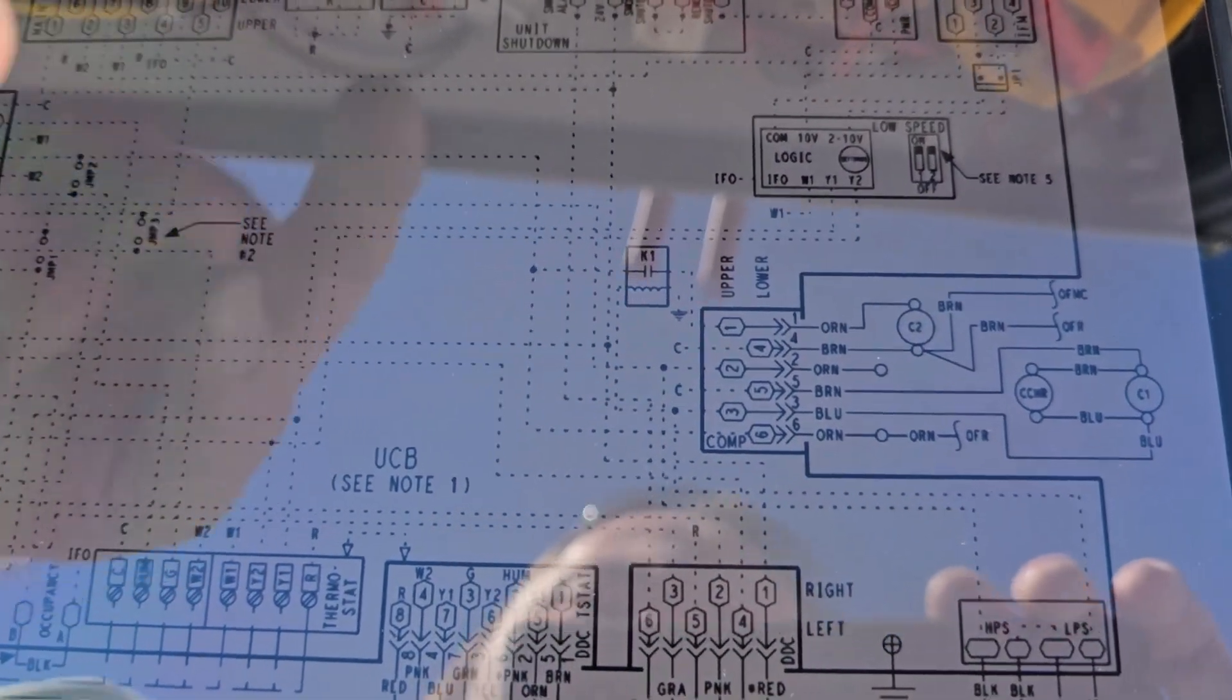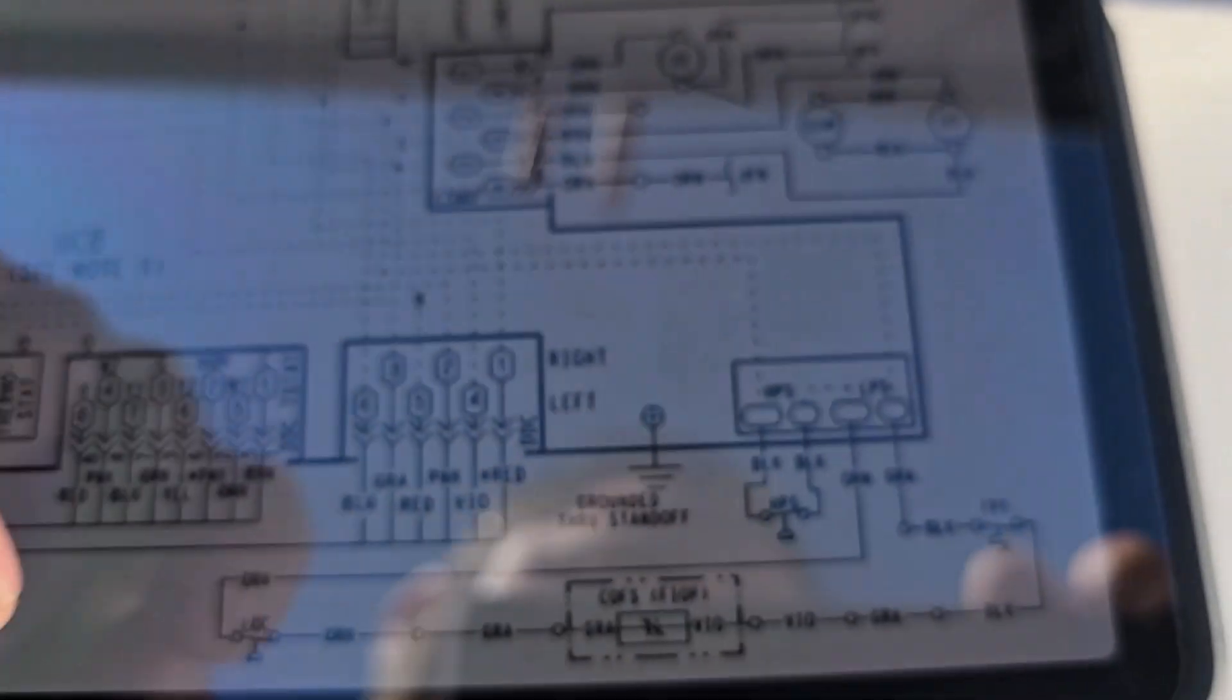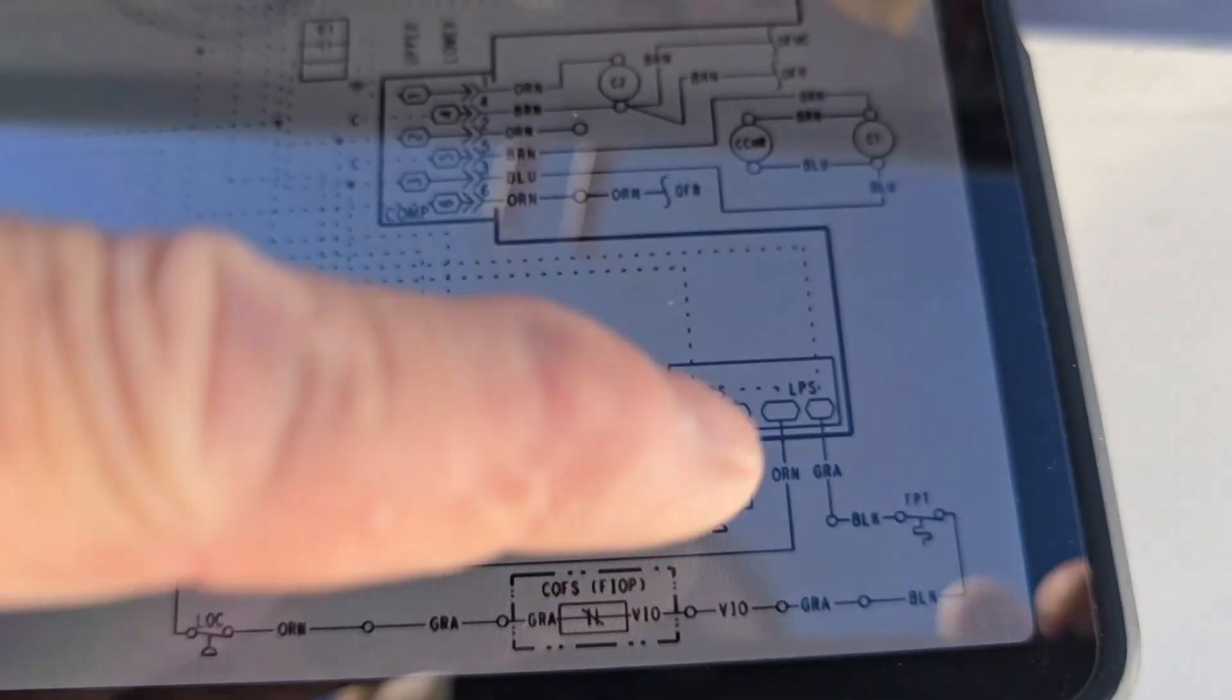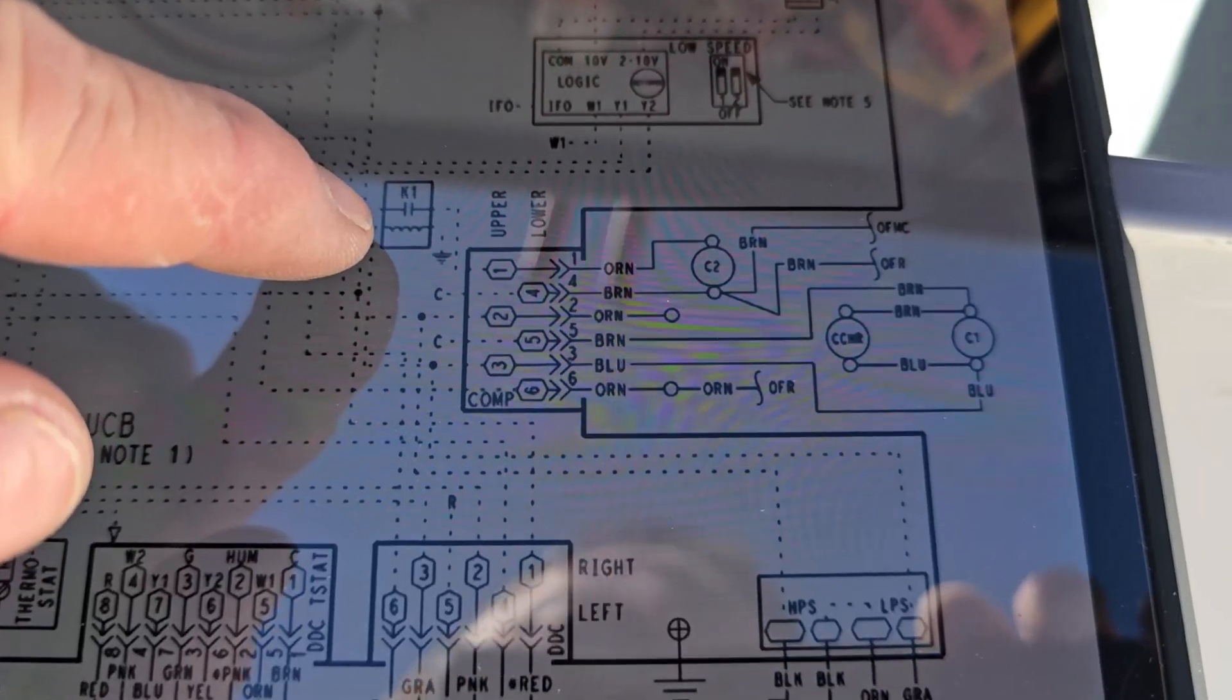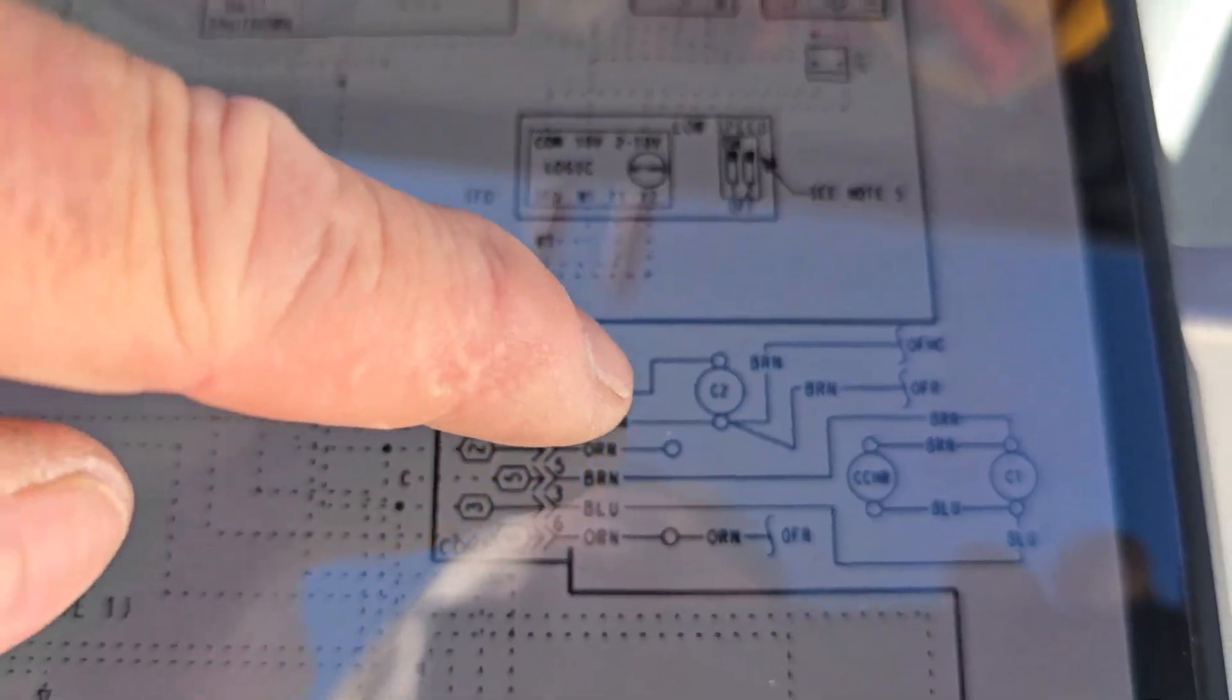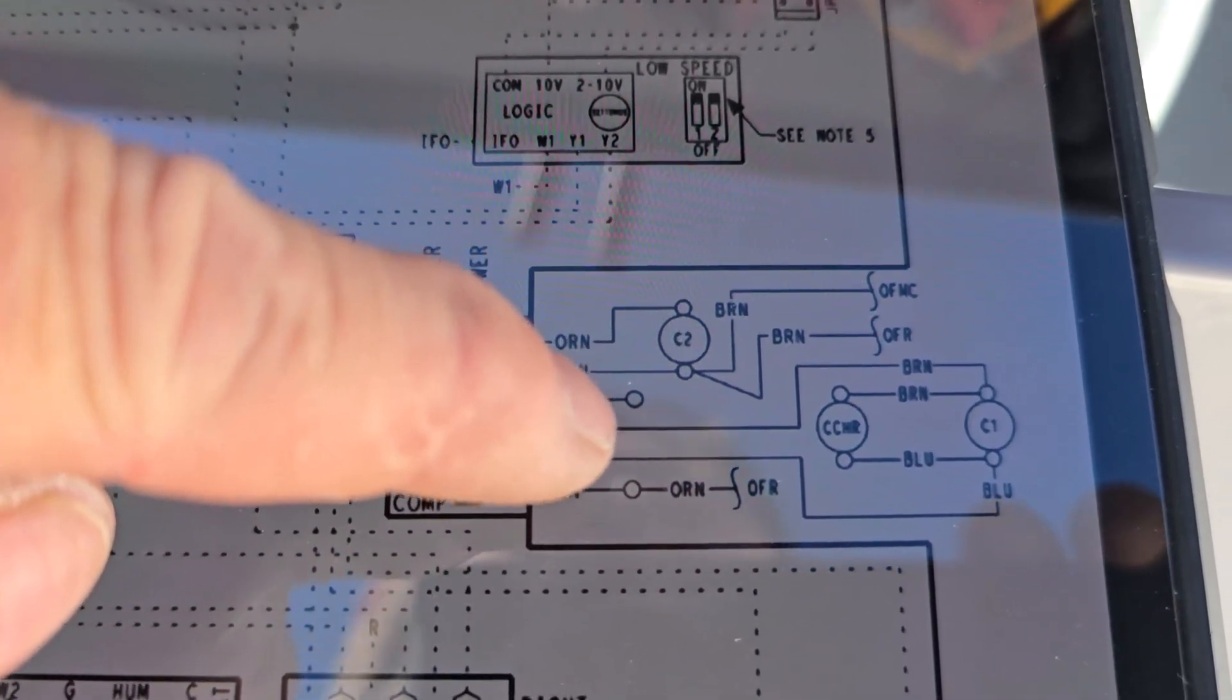So it's bypassing safeties and everything, because Y1 comes down and goes through your safety chain down here, you know, low pressure, high pressure, freeze stat, and then goes out, activates your K1 interlock relay, which is what allows Y2 to pass through it and go out to C2.